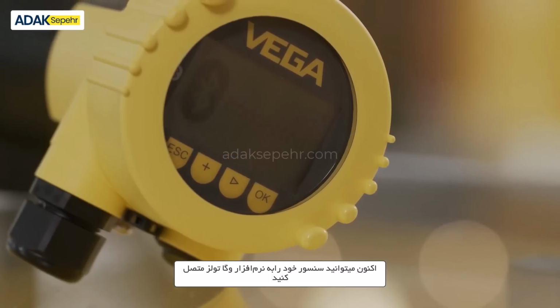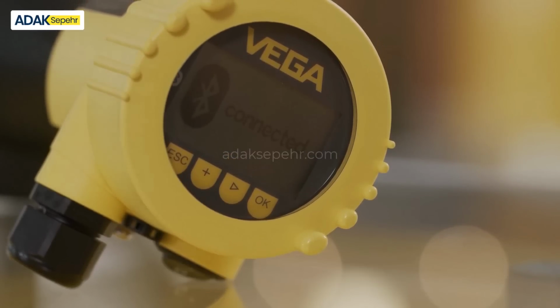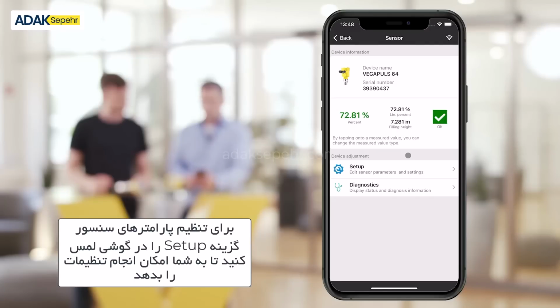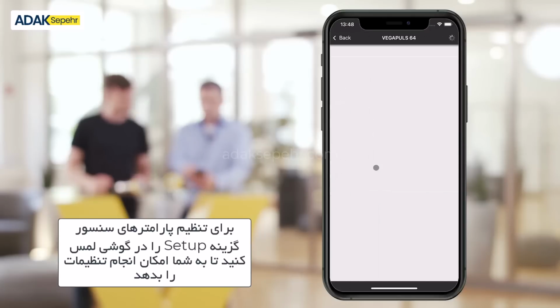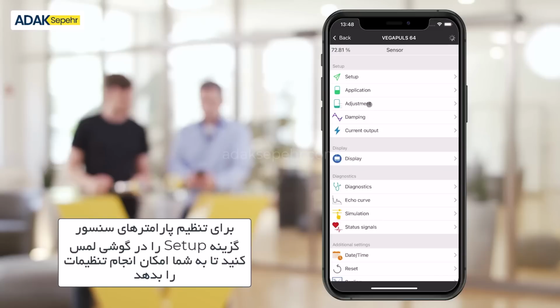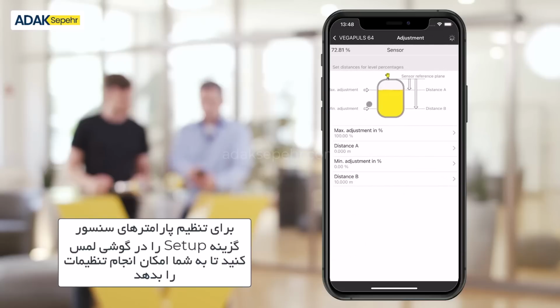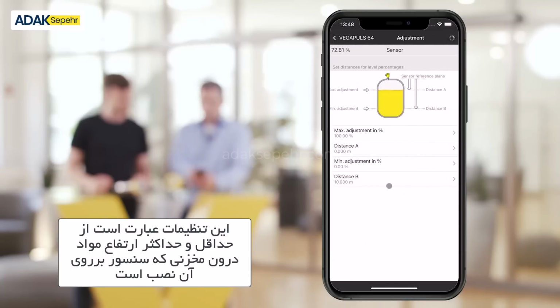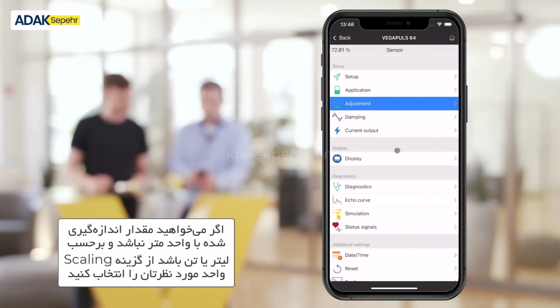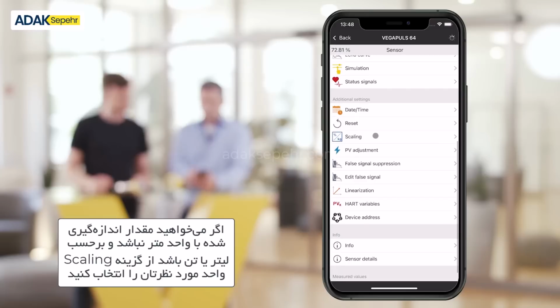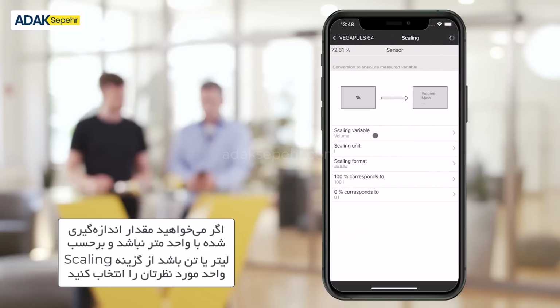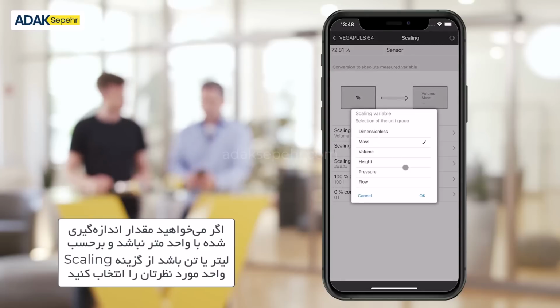Now I can connect to the Vega Tools app. To put the sensor into operation, we switch to the Setup menu, which allows us to carry out necessary settings, min-max adjustments, for example. If the measured value is not to be output in meters, but in liters or tons, this can be changed via scaling.